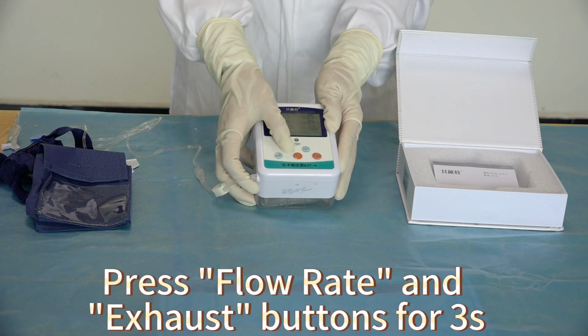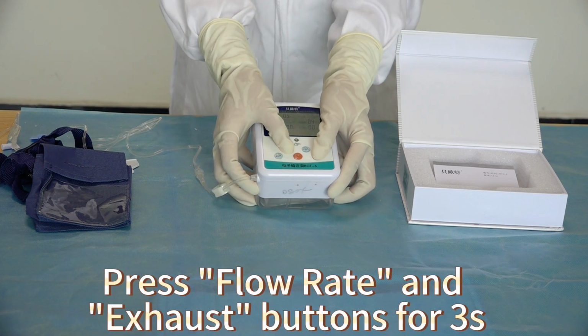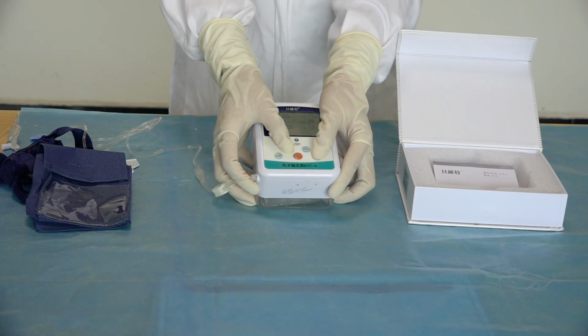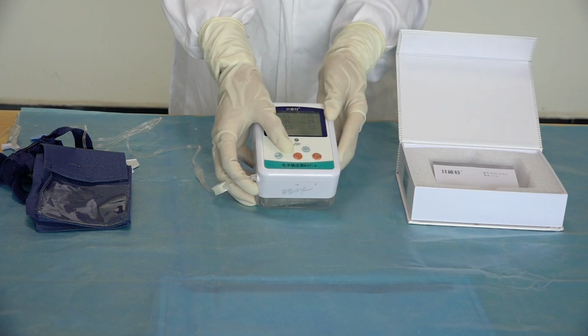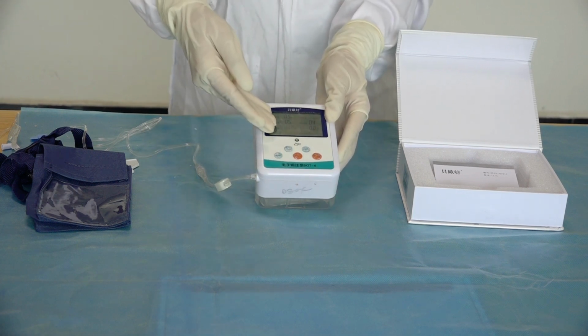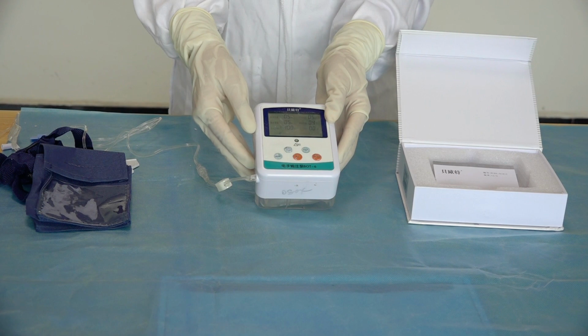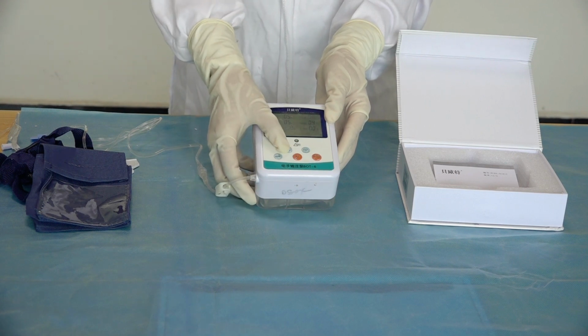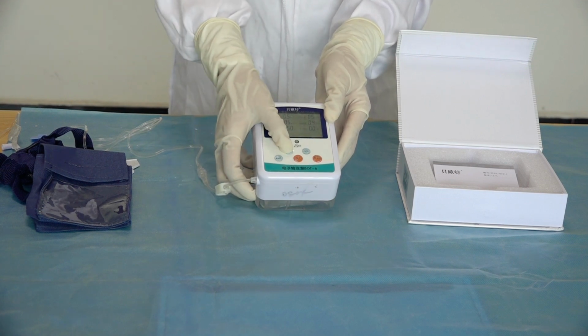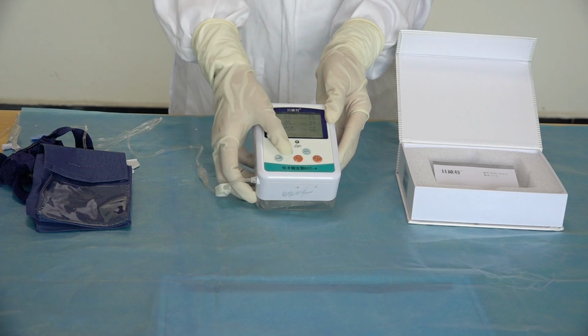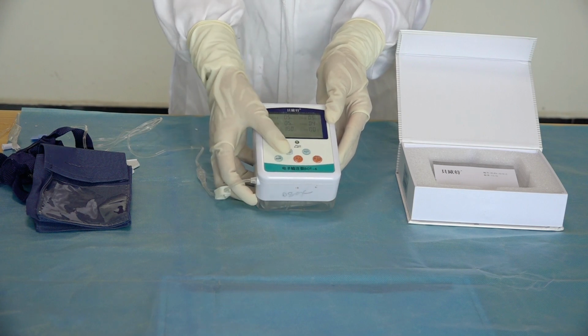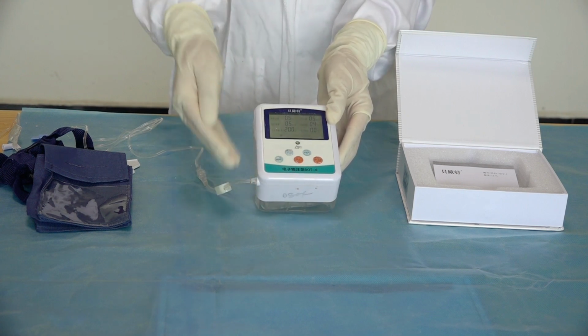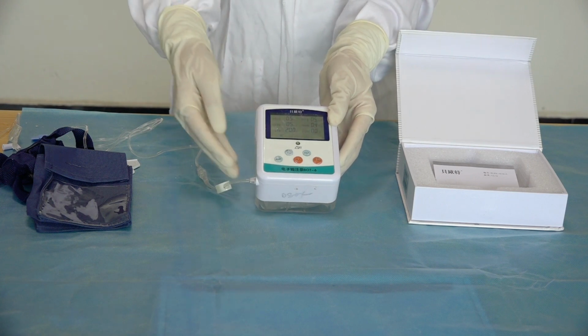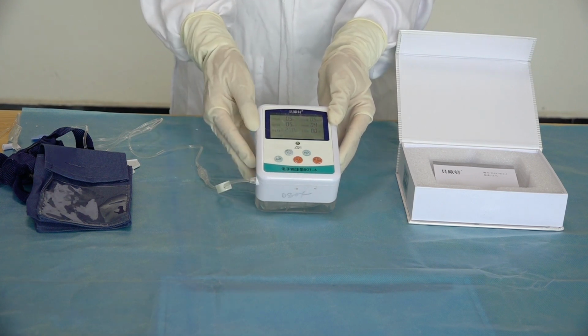Press the flow rate and exhaust buttons in the meanwhile for 3 seconds. The electronic infusion pump will emit a bleep sound D and the infused volume value will flash, for switching of nominal volume. The nominal volume can be set in 100 ml, 150 ml and 200 ml. Nominal volume means how much medicine needs to be infused.